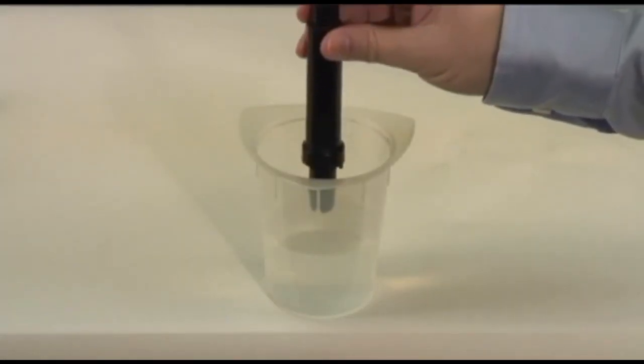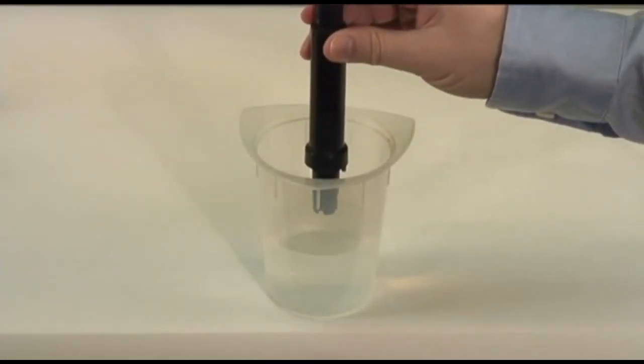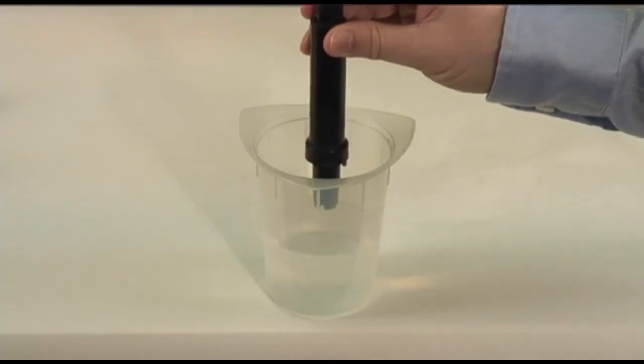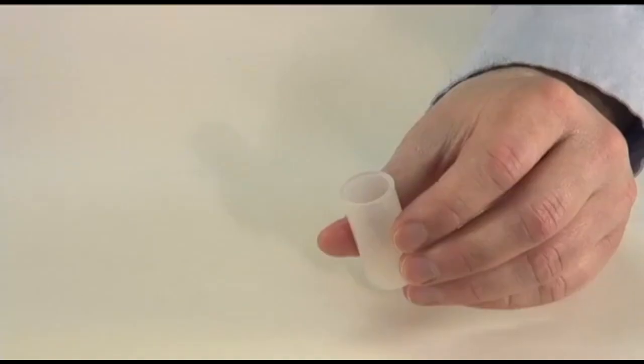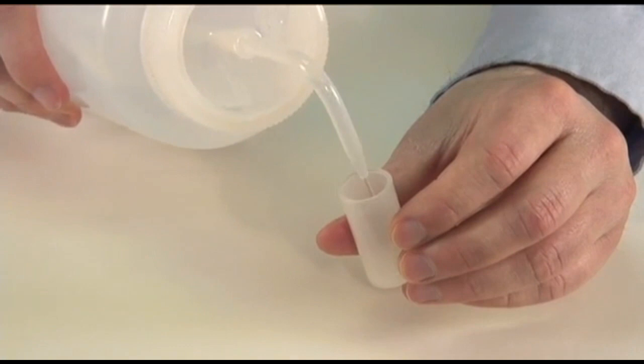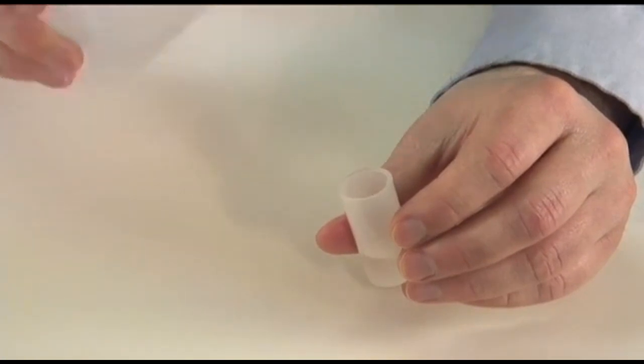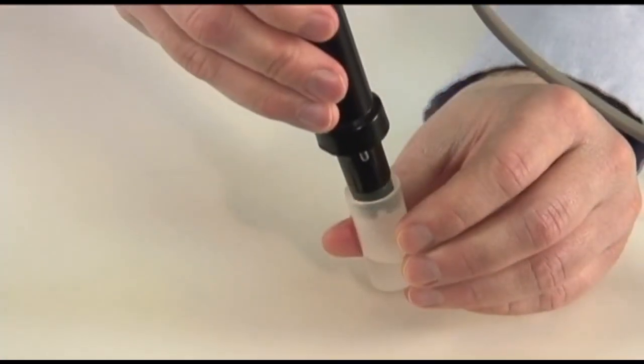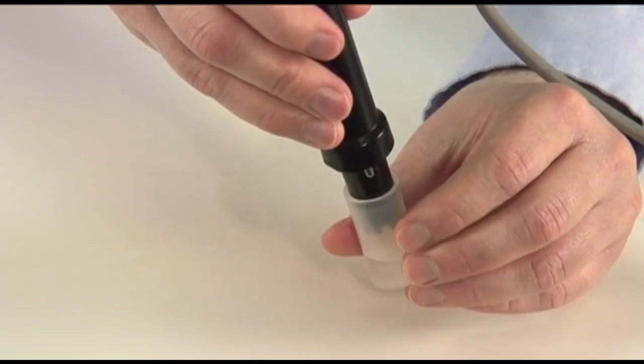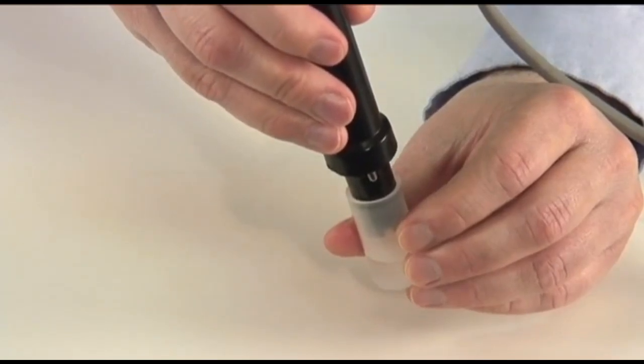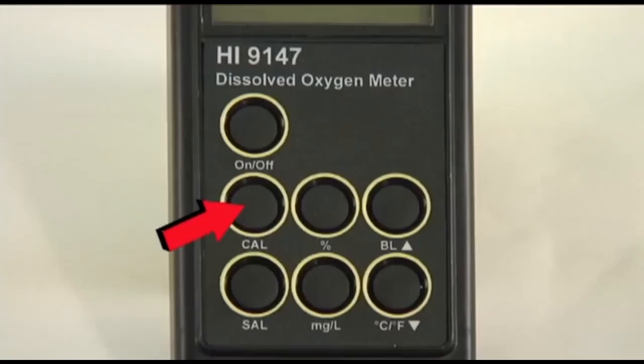Keeping the probe facing downwards as normal, hold the probe in air over a sample of water, but don't submerge it. Alternatively, you can fill the protective cap with a few milliliters of water and place the probe inside, over the water. Don't submerge it again. Also, don't forget to dump out the water when finished. Press the cal button.